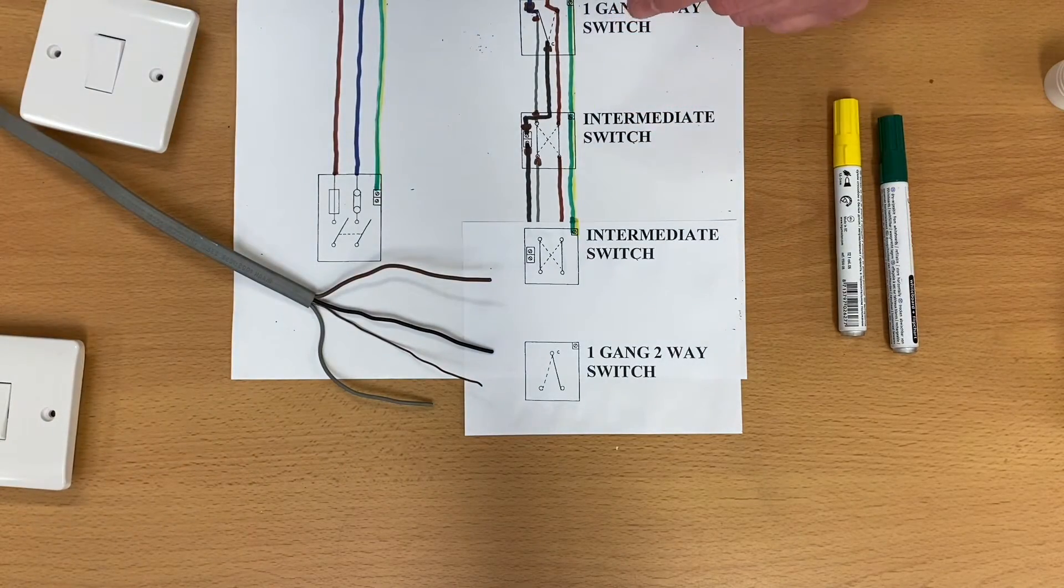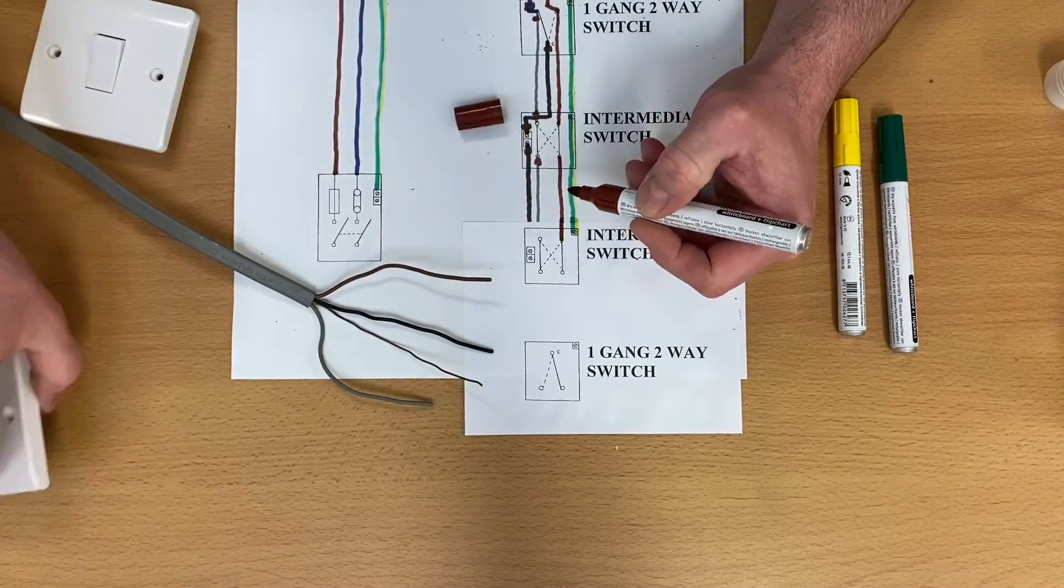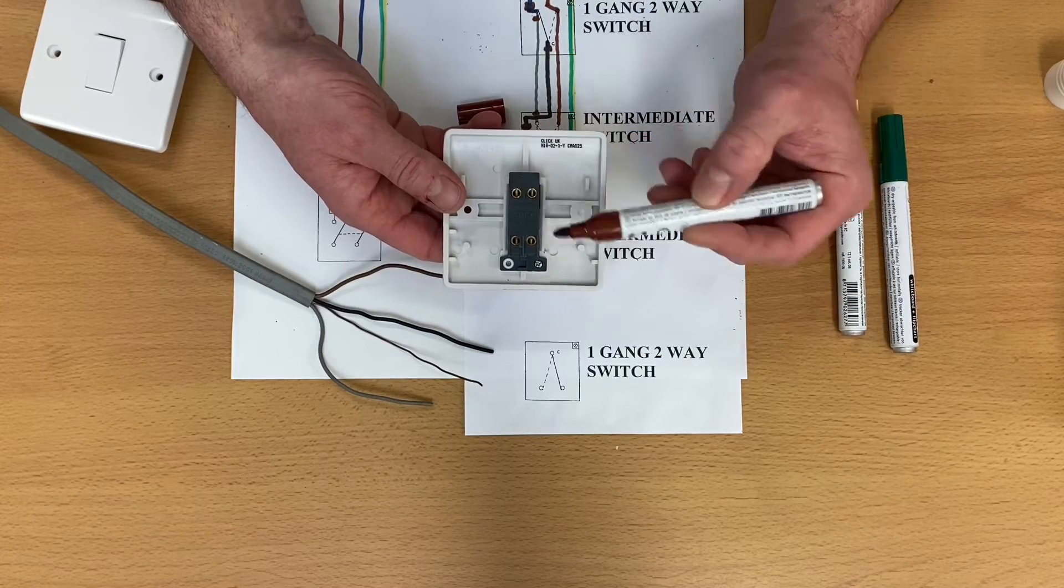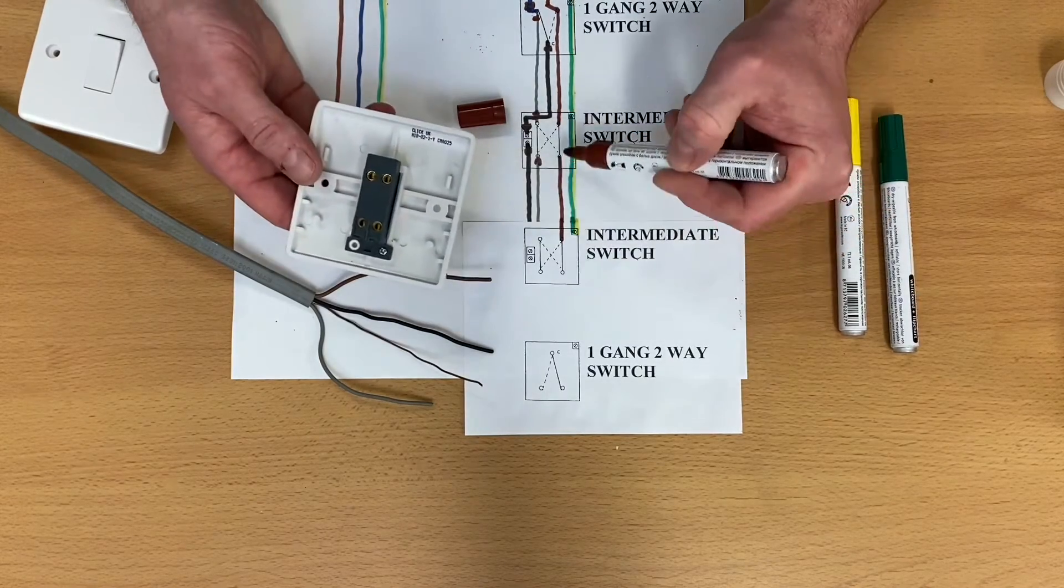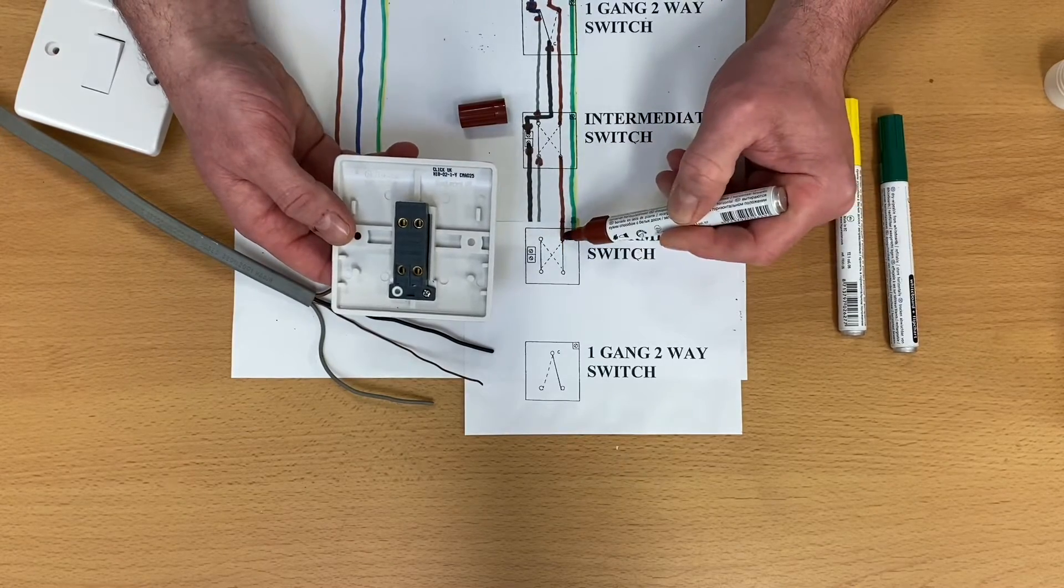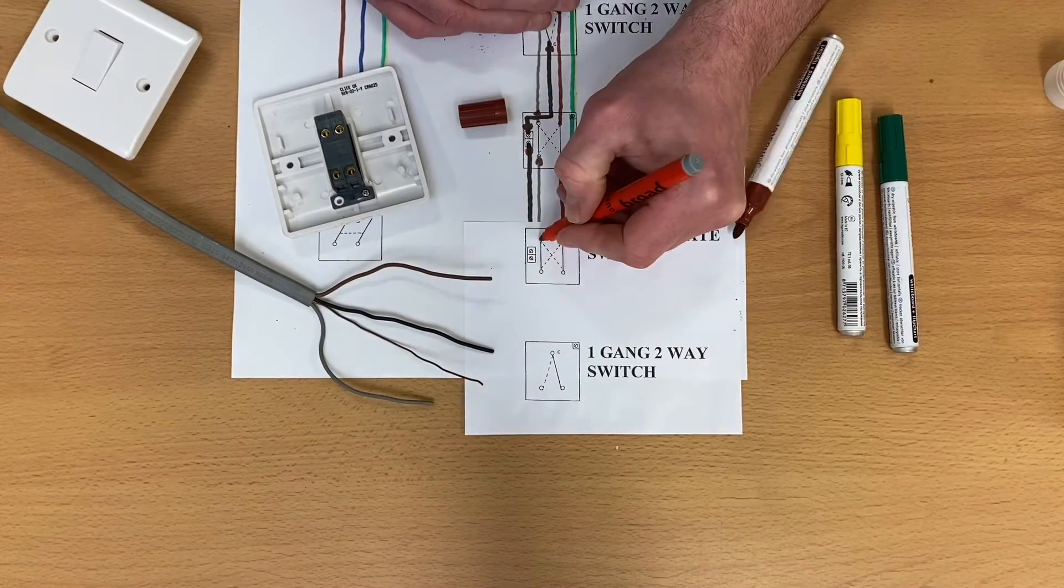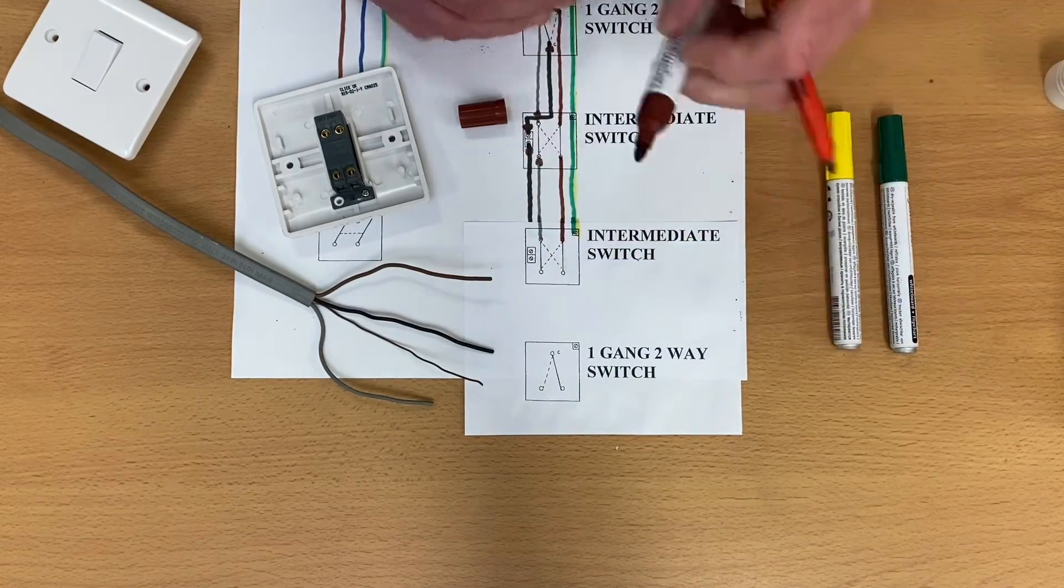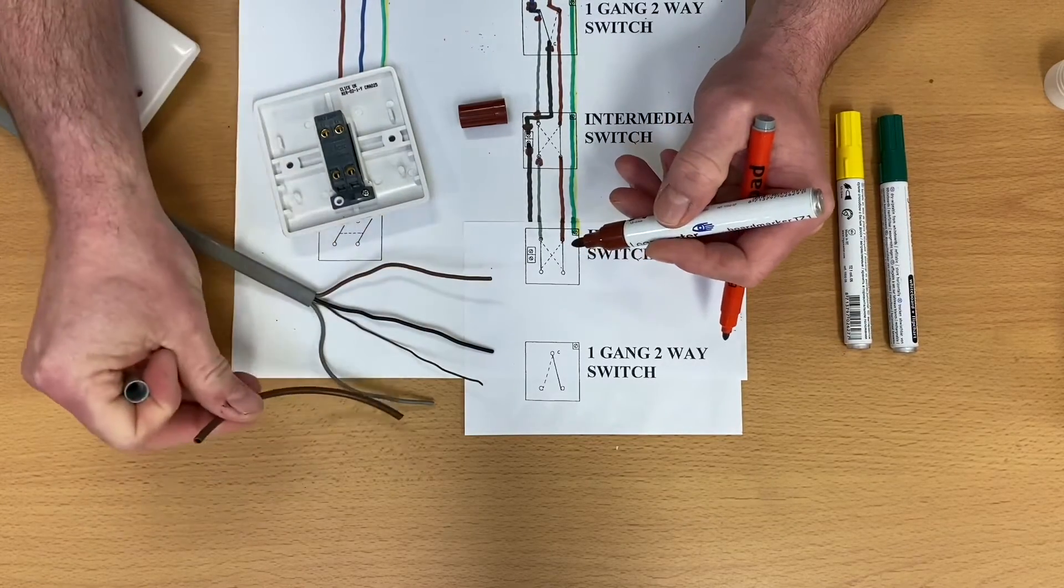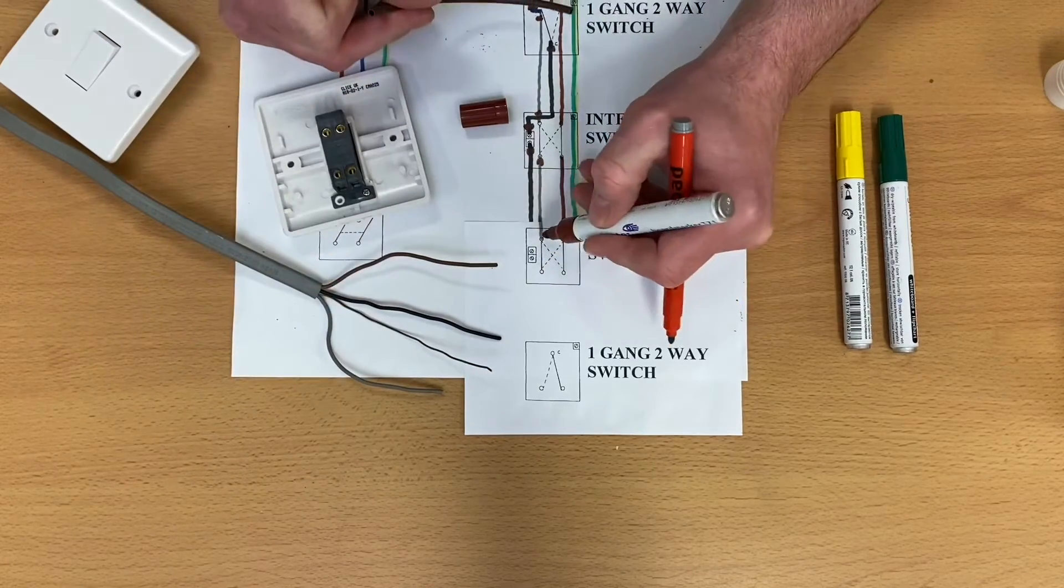We've still got the three-core. So we bring the brown down. The brown now goes into intermediate switch. Remember on the intermediate switch, we are either in the top two terminals or the bottom two terminals. So this three-core coming down, I'm effectively putting into the top two terminals. So the brown one goes in here. We've got our grey conductor, which again will need to be identified with brown sleeving. Remember, as it's a switching line conductor, we'll have to oversleeve our grey conductor and our black conductor in order to identify them as switching lines.